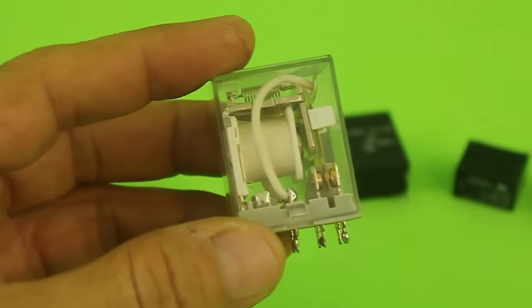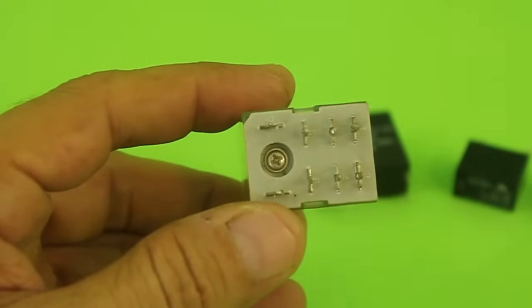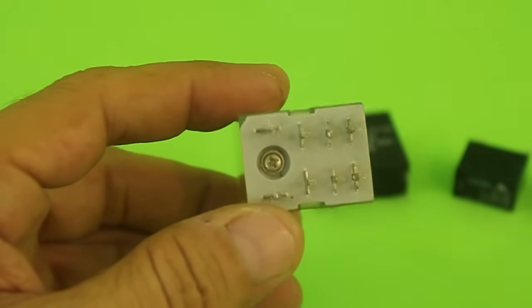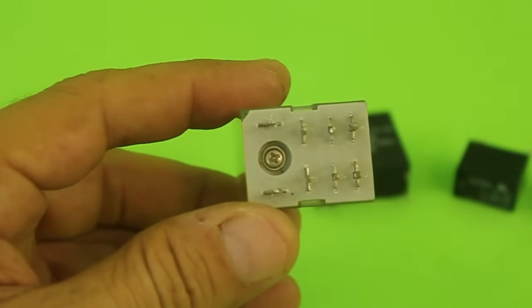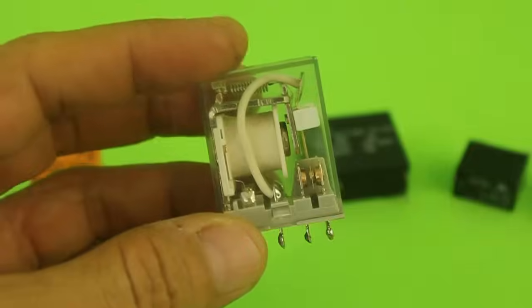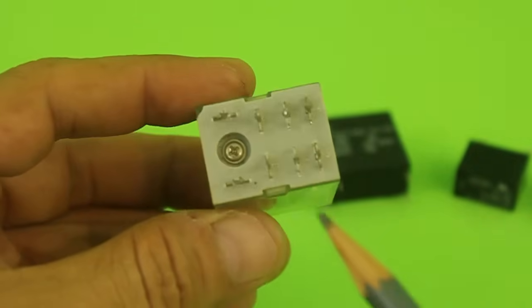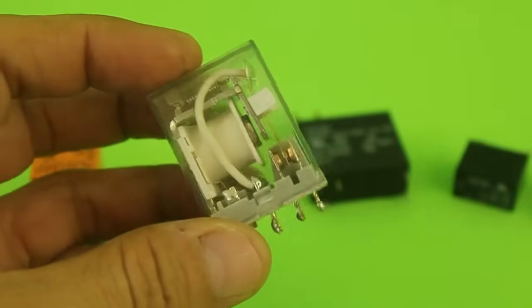Of some hundred ohms. So, it is easy to identify the pair that corresponds to the coil because you will measure some resistance in that pair. All other pairs of contacts will only give you continuity or not because they correspond to the contacts.